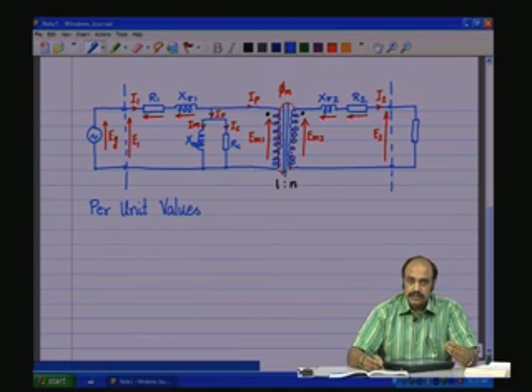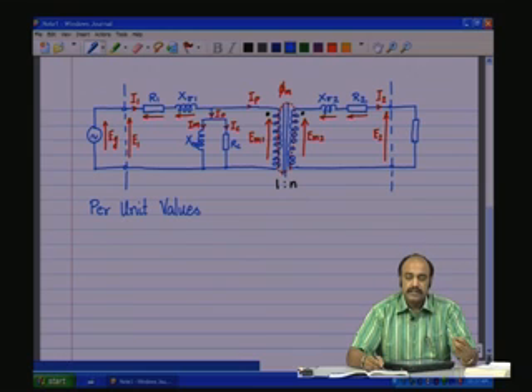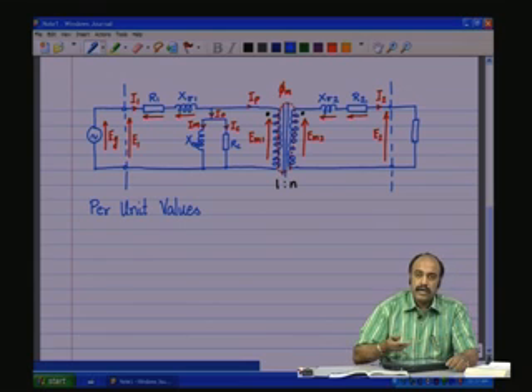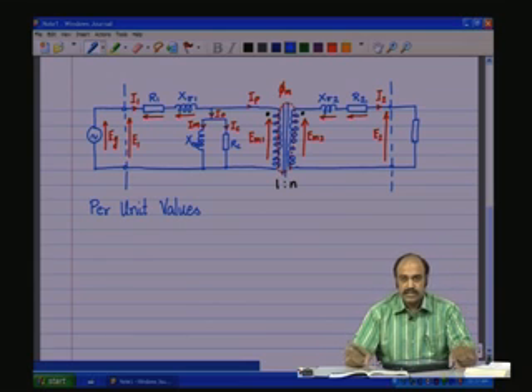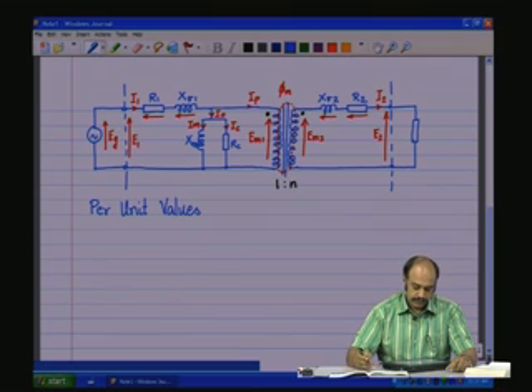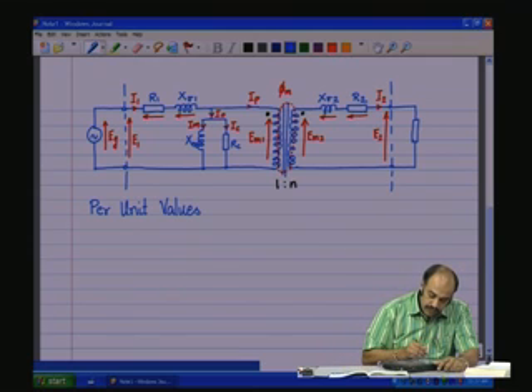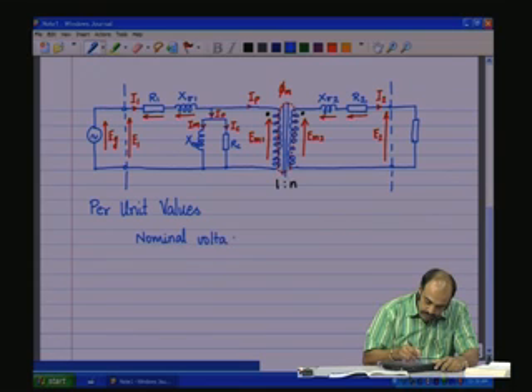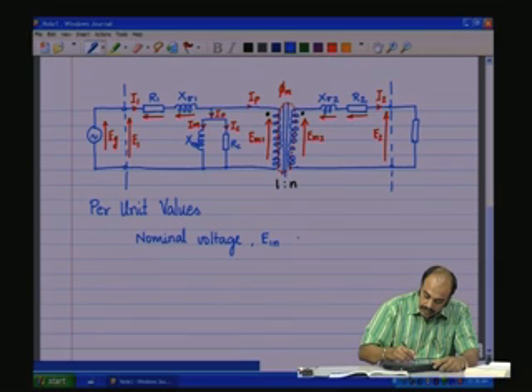So, if any value is 80%, then we say that it is 0.8 times the base value. So, that would give you a platform for comparison of the various transformers and of various ratings. Now, in the case of the per unit values, the nominal voltage of the transformer, that is E1 nominal, is considered as the base voltage.